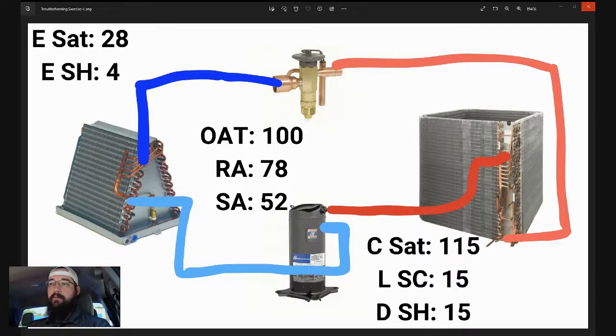Usually somebody asks, so I'll go ahead and restate. Discharge superheat is the difference between the condenser saturation, and if you want to get real specific, your discharge saturation coming out of the compressor, and you want to take a temperature reading on the discharge line about 6 inches off the compressor. That temperature reading from your saturation gives you discharge superheat.